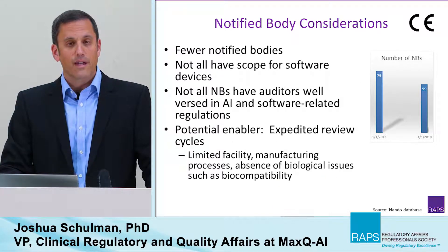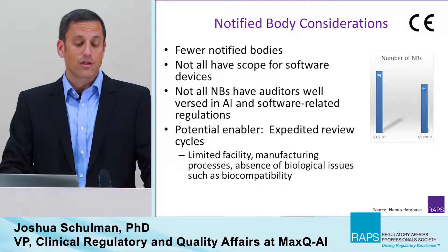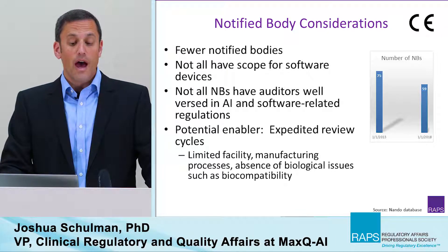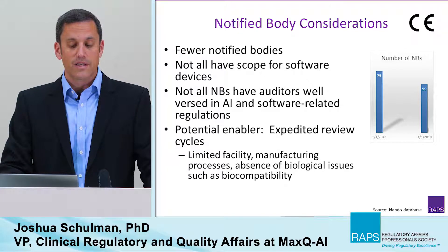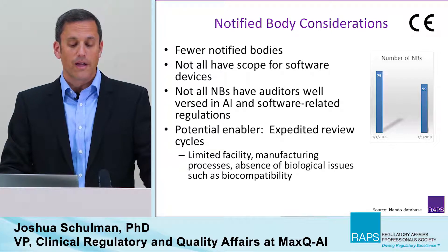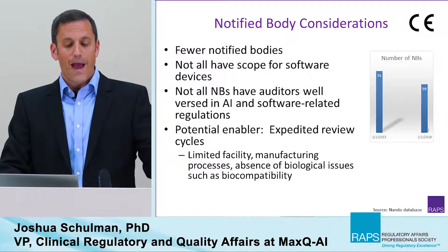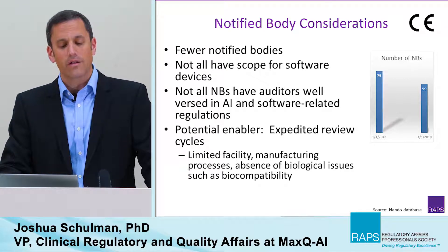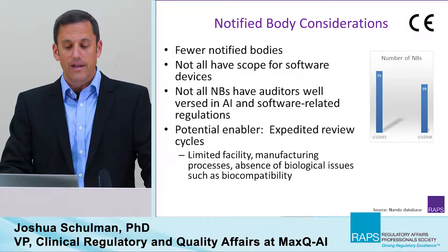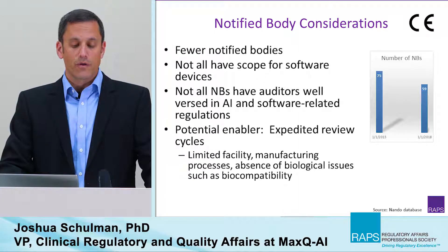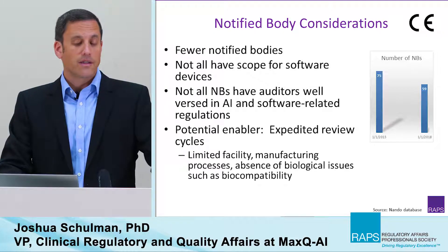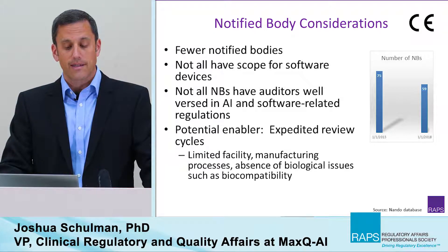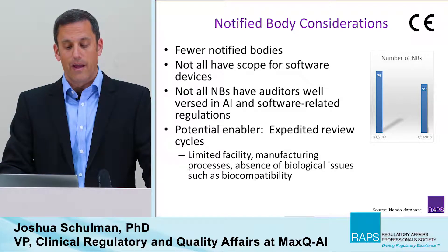Finally, we mentioned notified body considerations. As we mentioned, there are fewer notified bodies available. Not all of them have scope for software devices, and not all notified bodies have auditors who are well versed in AI and software related regulations. Sometimes during an audit, this requires additional explanation or additional background for the auditors. One potential enabler in this space is that some notified bodies are including expedited review cycles. These are well suited to software devices and AI devices in particular because there's limited facility and manufacturing processes, and there are really no biological issues such as biocompatibility.